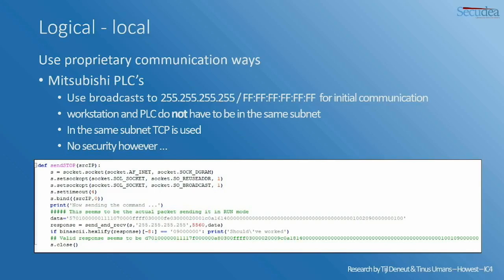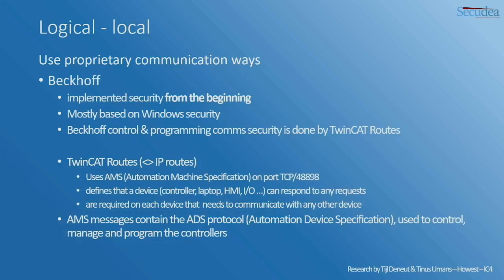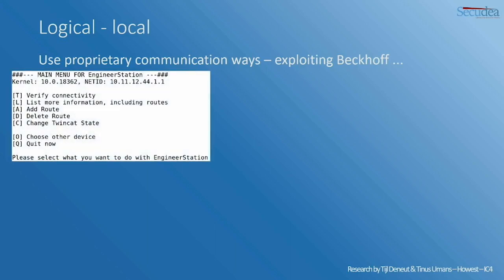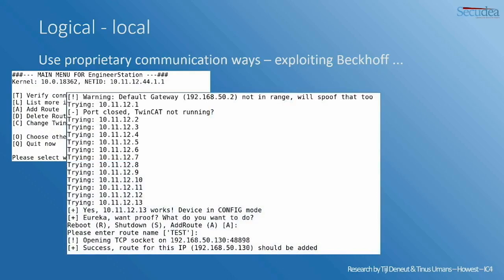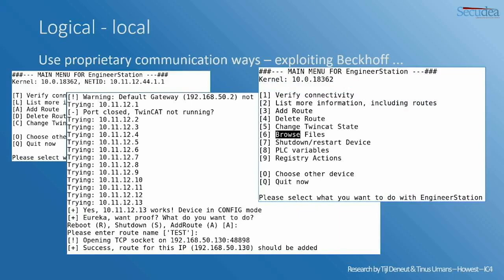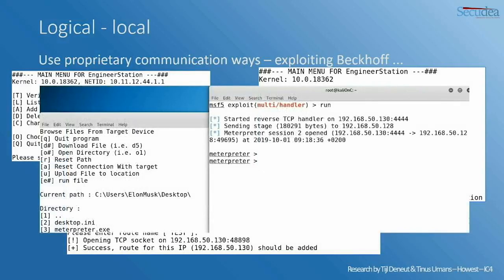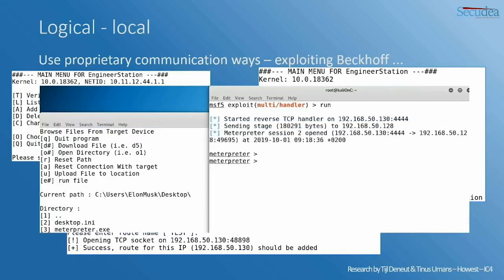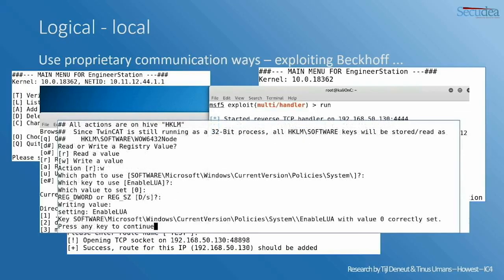On proprietary communication in the Beckhoff style: they do implement security, but it's based on TwinCAT routes and you can play around with those routes. I'll just show screenshots Tinus created to exploit Beckhoff systems. Verifying communication, connectivity to the device, add route, delete route — he found a system and could choose: reboot, shutdown, or add routes. If he got access to the engineering station, he could verify communication, browse files, upload files — upload something like Meterpreter, because Beckhoff is actually a Windows system — and get a nice Meterpreter shell. You can browse and change the registry, all on a fully patched Windows system, accessed through engineering software.